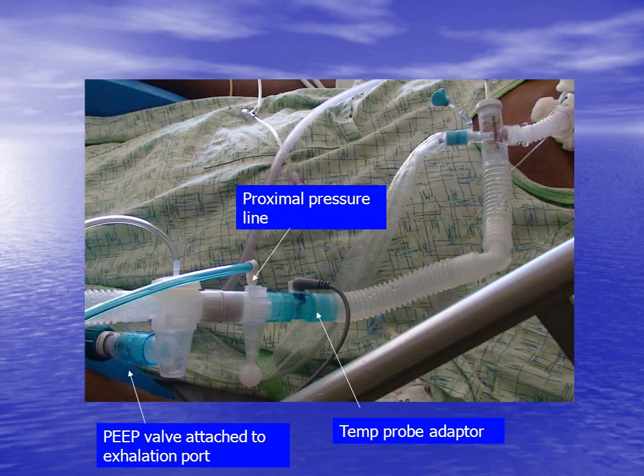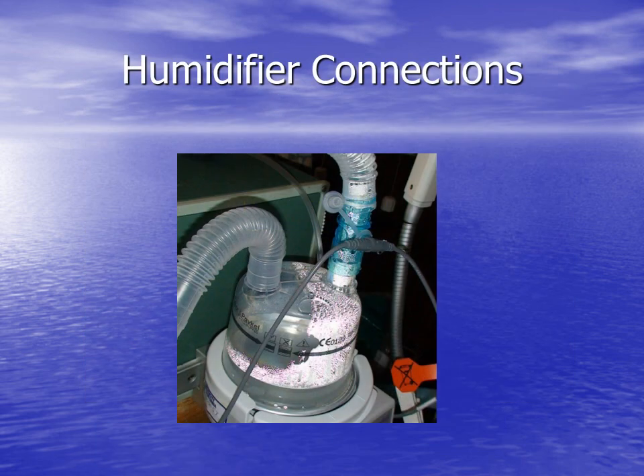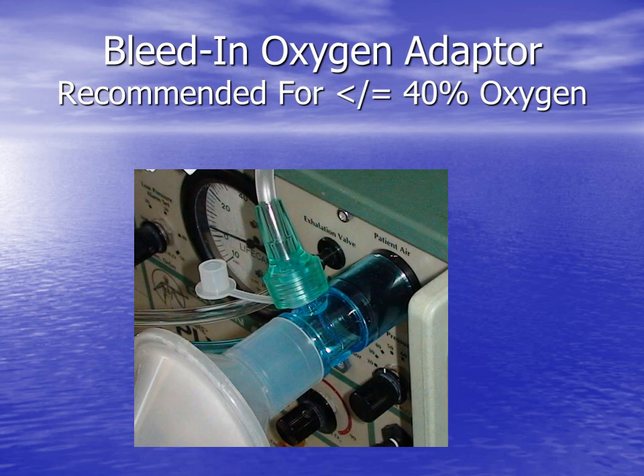PEEP may be generated with the placement of an external adjustable PEEP knob after the exhalation valve. Here we also see the addition of a temperature probe adapter proximal to the patient, as well as a closed suction system. Here is a second temperature probe adapter placed on the wet side of the humidifier to ensure proper functioning of a dual probe humidification system. Here is a closer look at the oxygen bleed-in assembly.